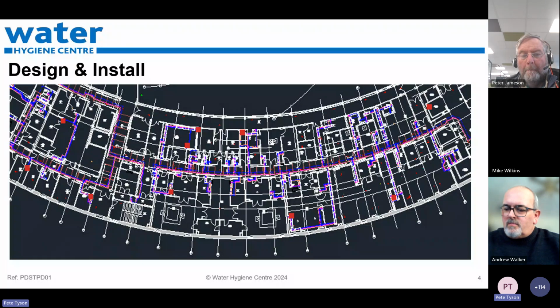HSG 274 Part 2, paragraph 2.48 details the stagnation of the water system during construction time as being a potential issue for biofilm formation, and as such, bi-weekly or twice a week flushing alone will not suffice. And the contractors do not appreciate that water sat around only being flushed twice a week presents a risk, especially when they've left site. So we need to make sure we've got daily flushing with the addition of chlorine dioxide, for example, 1 to 3 ppm is suggested as a means to reduce the risk of biofilm formation.